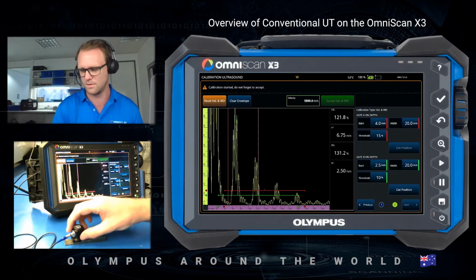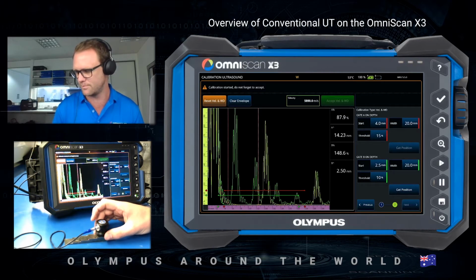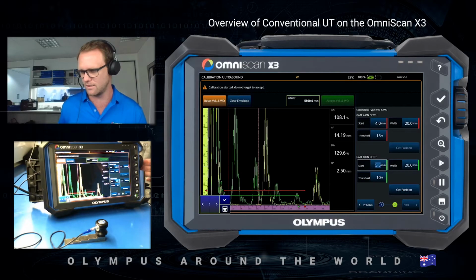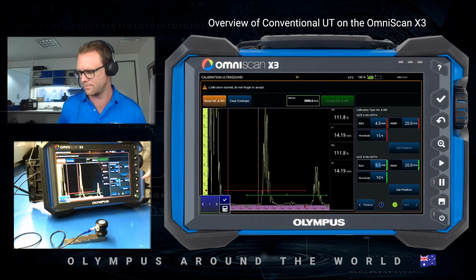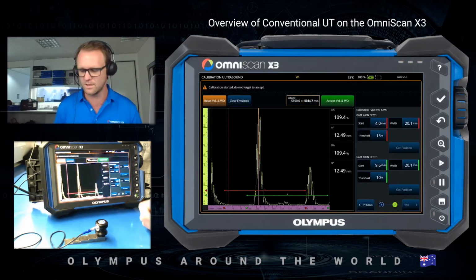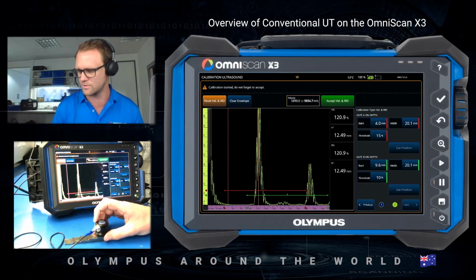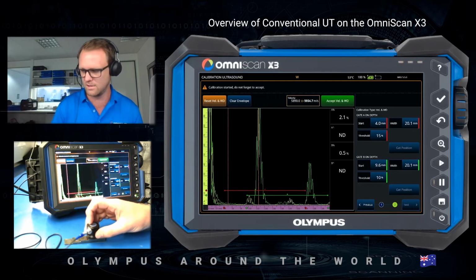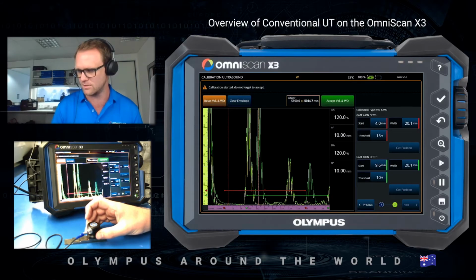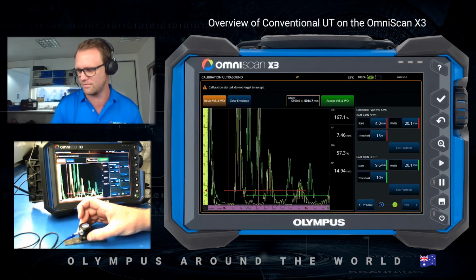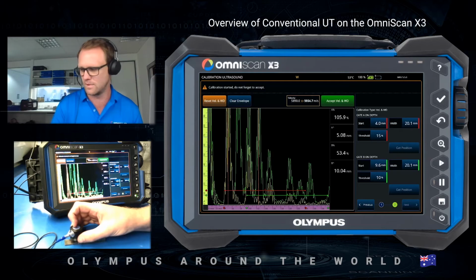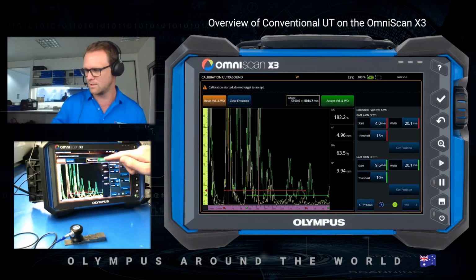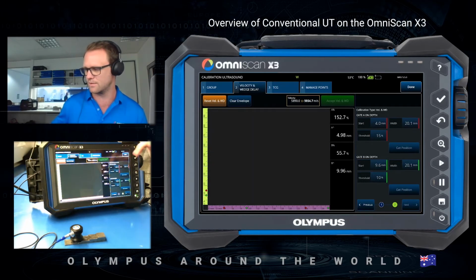I can get that position. Move my probe onto the 12.5, and then make sure my gate again is not hitting the initial pulse. I'll get that position. So now I can just validate my calibration is correct. So you can see within the screen here, I'm on the 12.5 step and reading 12.5. If I go to the 7.5, we now need to look at, sorry, this is the 10mm. See, that's reading 10. 7.5 on gate A is reading 7.5. And this is the 5mm. So on gate A, we're reading at 5mm. So I'm going to accept that and press done.